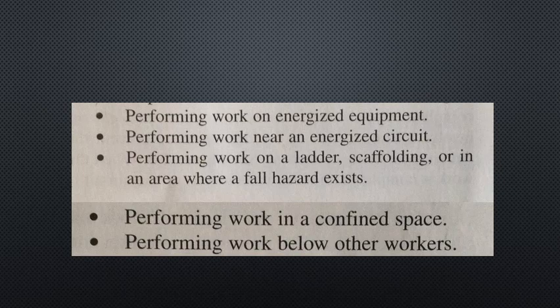When a fall hazard exists, always use non-conducting fiberglass ladders. An aluminum ladder can become energized if a live conductor comes in contact with it. Confined spaces such as trenches, tunnels, and manholes present many hazards. Tight working conditions make careful work difficult, and inadequate oxygen supply and the presence of explosive or poisonous gases are additional hazards. A worker should be posted outside the confined space to get help if an accident occurs. Work should never be performed below other workers without proper precautions; a physical barrier should protect lower workers from falling debris, including tools.